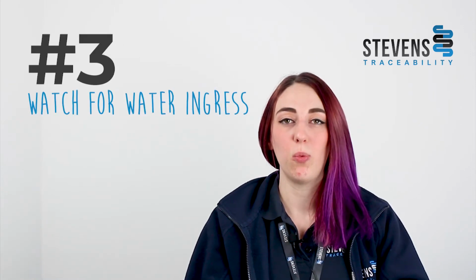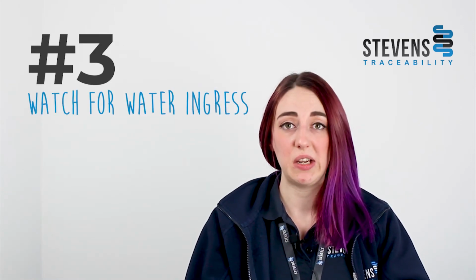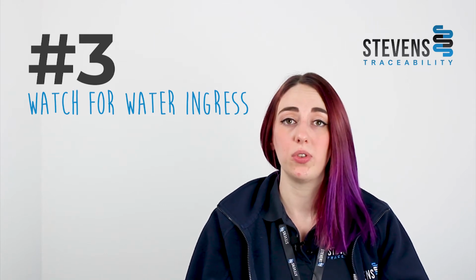Tip number 3 is about water ingress. We discussed earlier about cleaning your scale. Quite often on hygiene sites, you will have a jet washer which is used to clean the scales. Jet washing could cause water ingress into part of your scale. In the indicator, you can get things which will affect the internal electronics. If you see anything such as condensation on the outside, you could have water ingress on the inside.